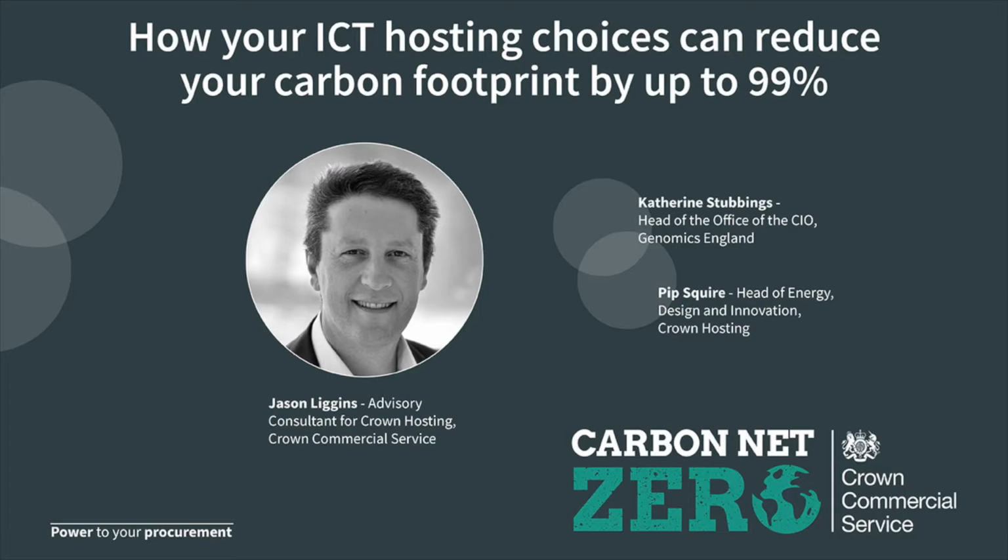In a data center or a cloud facility, they have similar operating efficiencies with a power usage effectiveness of typically less than 1.2. By this, I mean for every 100 kilowatts of power used by the IT systems, the facility only needs around 20 kilowatts of parasitic load to support it. That's a huge reduction in power demand. And as I've said before, the hyperscale facilities just offer economies of scale.